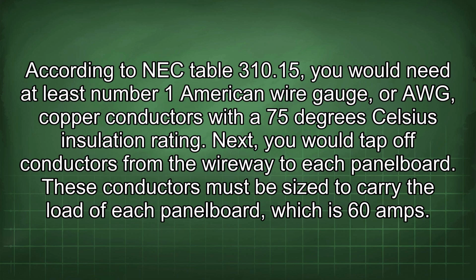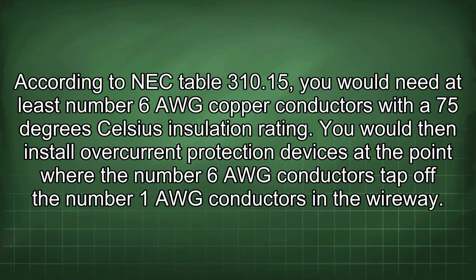According to NEC Table 310.15, you would need at least number 1 American wire gauge (AWG) copper conductors with a 75 degrees Celsius insulation rating. Next, you would tap off conductors from the wireway to each panel board. These conductors must be sized to carry the load of each panel board, which is 60 amps.